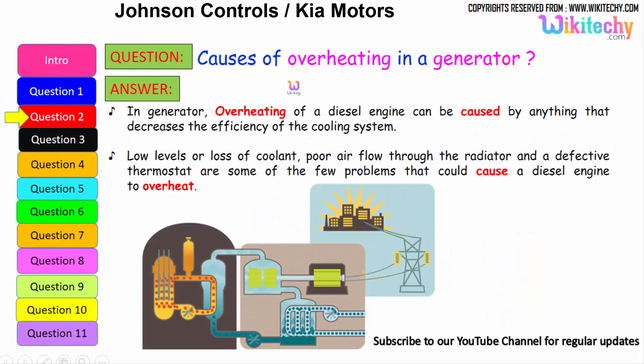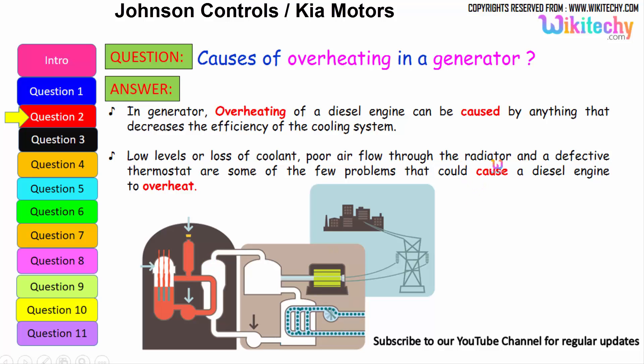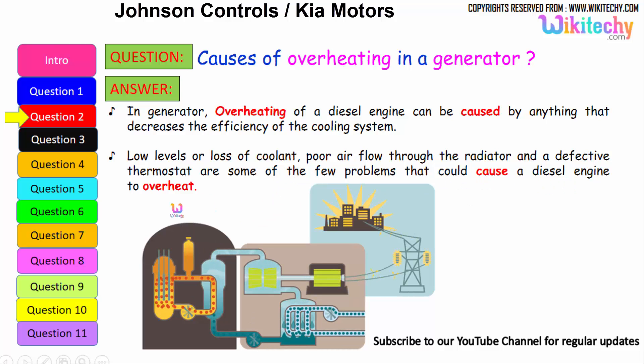Let's move on to the next question: causes of overheating in a generator. Overheating of a diesel engine can be caused by anything that decreases the efficiency of the cooling system. It can be due to loss of coolant, low levels of coolant, poor air flow through the radiators, and a defective thermostat — some of the few problems that could cause a diesel engine or generator to overheat.